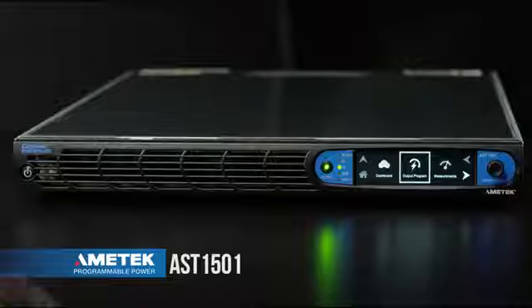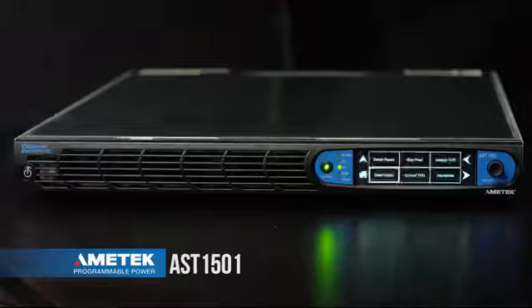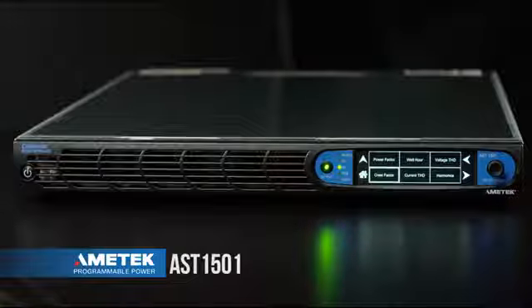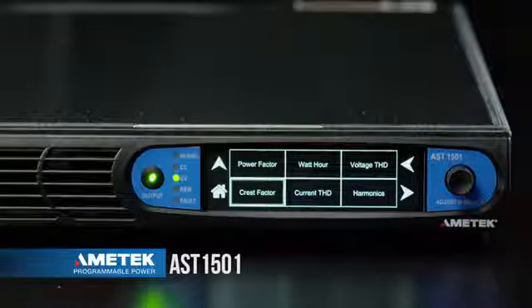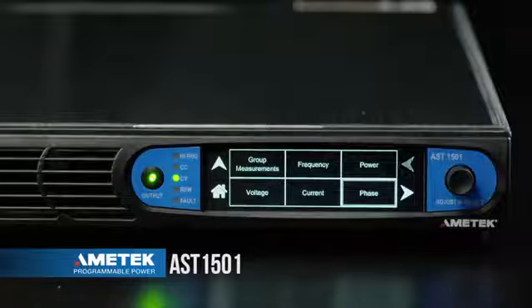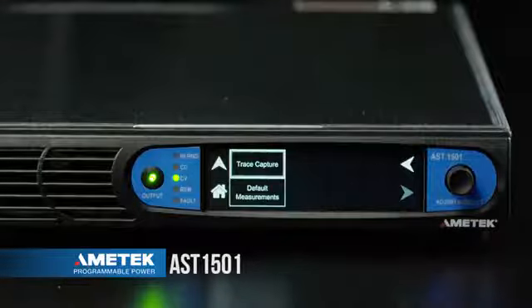Next up is measurements. By selecting measurements, we're presented with a list of measurements that we can make. We can make power factor, watt hour, voltage distortion, crest factor, current harmonic distortion, harmonics. Going to the left, we have a group of measurements: frequency, power, voltage, current, and phase angle. Going to the full right, we can do a trace capture and set what our default measurements are.